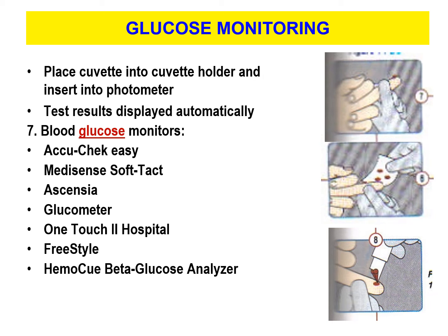What you always want to make sure is wherever you're working, whether they're using an AccuCheck, a One Touch, a Freestyle, there is a ton of different glucose bedside monitors out there, and you want to make sure that you follow the specific guidelines for your particular monitor and follow the directions. Whatever strip or cuvette goes with that instrument, you want to make sure you use that one. Follow the directions the manufacturer set out for use with their particular monitor.